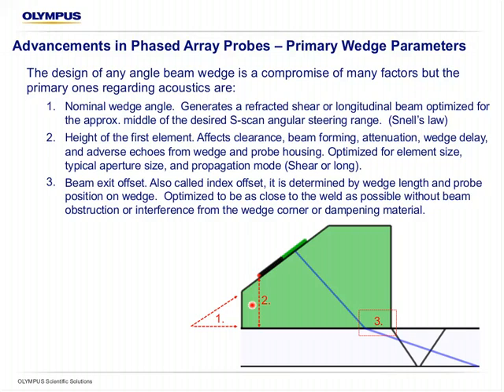The larger this parameter, the more wedge delay, and this can be used to avoid adverse echoes from the wedge and probe housing. This is also optimized for the element size, the typical aperture size used with the 16 or 32 pulser instrument, and propagation mode of either shear or long. The third parameter for consideration is the beam exit offset. We want the high angle exiting as close to this corner as possible for common probe apertures without interference from the dampening and without extraneous signals from the wedge corners. We want this as close to the weld as possible for maximum coverage on the first leg.